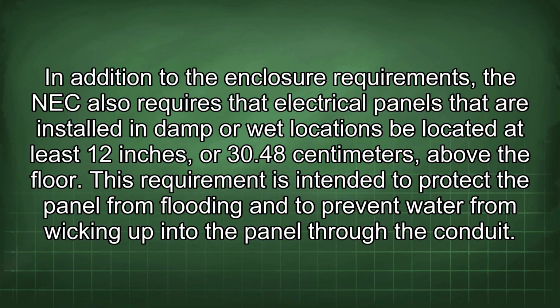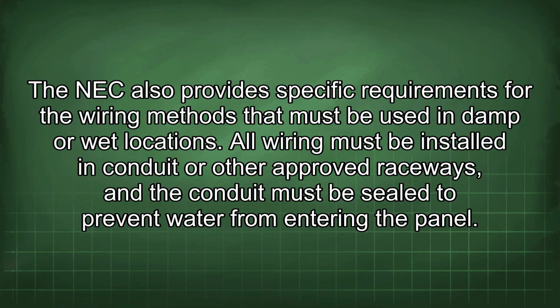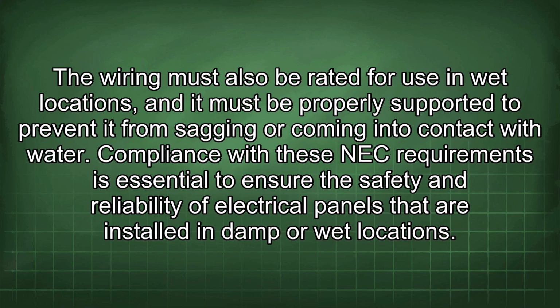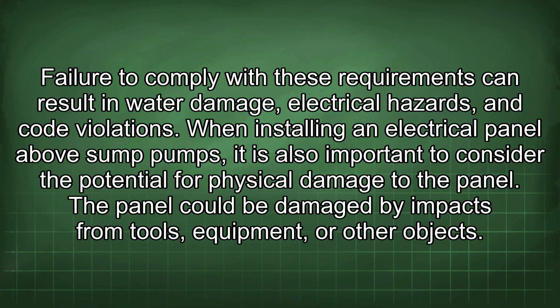through the conduit. The NEC also provides specific requirements for the wiring methods that must be used in damp or wet locations. All wiring must be installed in conduit or other approved raceways, and the conduit must be sealed to prevent water from entering the panel. The wiring must also be rated for use in wet locations, and it must be properly supported to prevent it from sagging or coming into contact with water. Compliance with these NEC requirements is essential to ensure the safety and reliability of electrical panels that are installed in damp or wet locations. Failure to comply with these requirements can result in water damage, electrical hazards, and code violations.